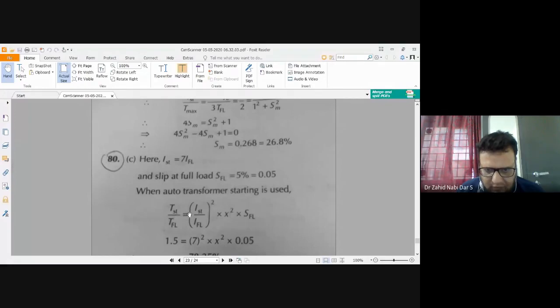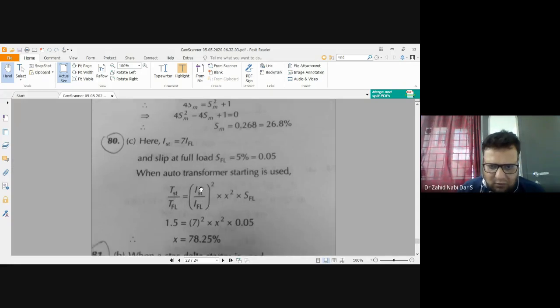Okay. So this would be IST square divided by ST, the starting slip, that is your 5%. And TFL would be equal to IFL square divided by your SFL. So now you can clearly see, your TST is directly proportional to IST square and inversely proportional to ST. So IST directly proportional, TFL directly proportional. Now inversely proportional is the ratio. This is the ratio. So this ratio you have to calculate. Let this ratio be X%.